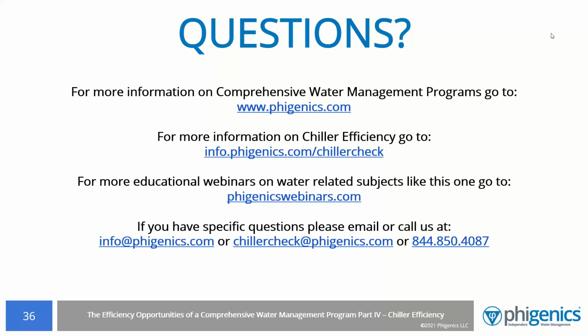Yeah. With the program that Mike and I were talking about, you enter operating data, you look at your condenser approaches, you calculate what we call your excess approach, and then you apply that to an efficiency loss formula. You typically are going to lose up to 2% efficiency for every 1 degree your approach is higher than it should be. So if you have a 10-degree excess approach, you could be losing 20% efficiency. And what some of the programs do is take that percent loss and apply it to a run hour calculation that predicts how many run hours and at what percent load your chiller typically runs per year. And you say, if we ran that whole year with that efficiency loss, what would it cost us in energy? And that gives you the ROI that Mike was talking about.